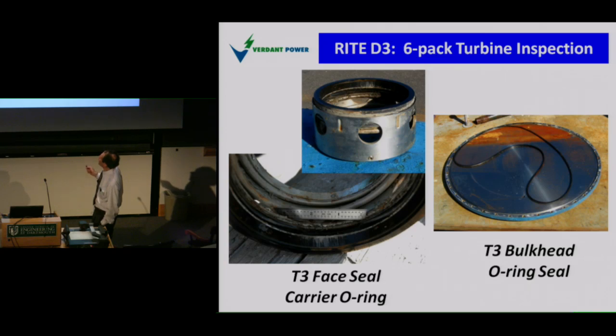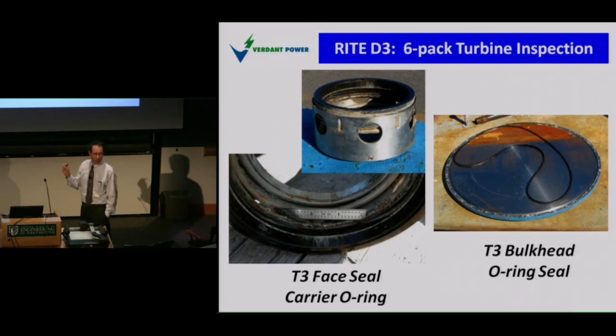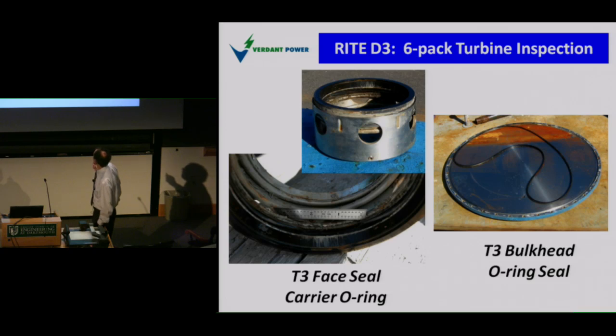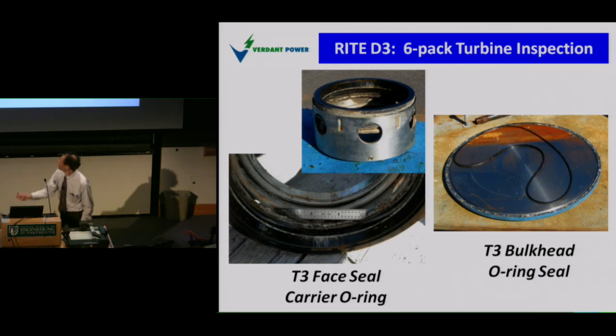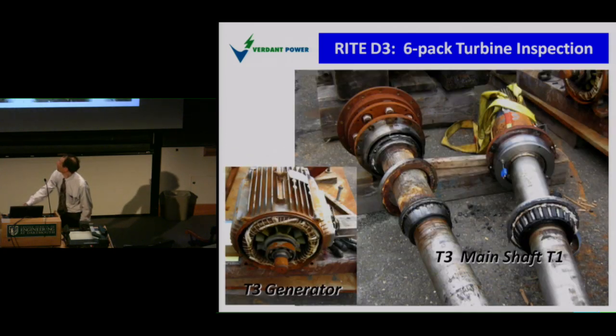Here's the graphite part of the carbon ceramic seal taken apart. Mirror finish, there's a tremendous amount of grit. Every open area near these turbines was full of grit, yet the faces were pristine. However, on turbine 3, when it was assembled, one of the O-rings on the carrier was damaged, so it's as if it wasn't even there. And you can see the watermarks inside the other bulkhead for turbine number 3. On turbine number 3, the O-ring there on both ends actually was fine. It was the assembly of the seal O-ring that failed.